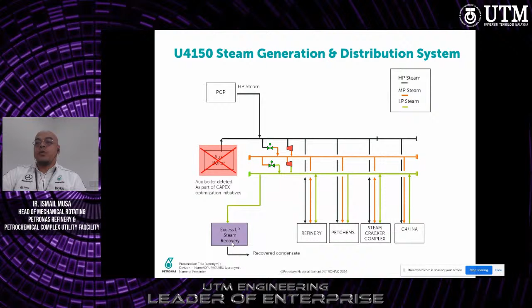This is the steam generation and distribution system. As you can see from here, from PCP, the cogen plant, we send the high pressure steam to all the refinery, the steam cracker complex, and also the petrochemical complex. The excess LP steam we send to the condensate recovery. For your information, the excess LP steam can also give a saving to the company. And last year we embarked on a new project: installing a condensing turbine to use the excess LP steam, so we can generate more power, about 16 to 20 megawatt.